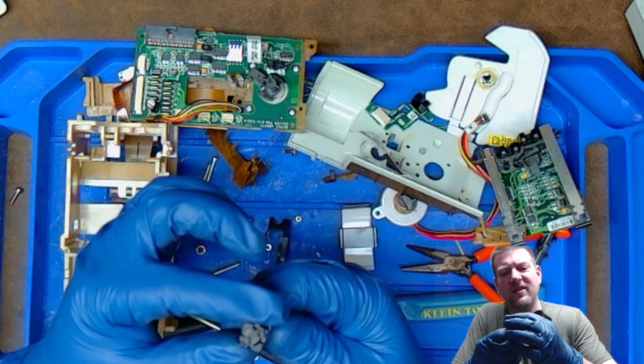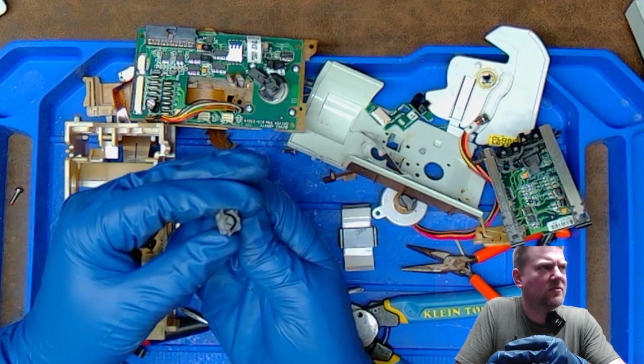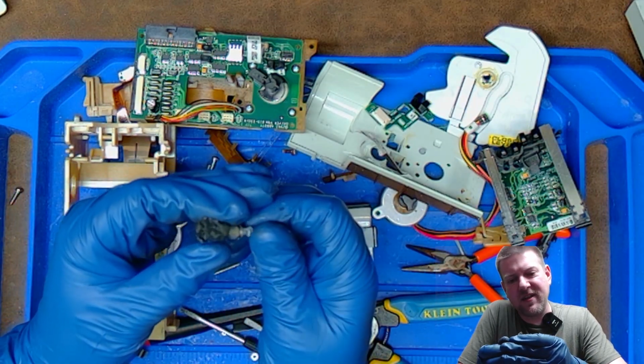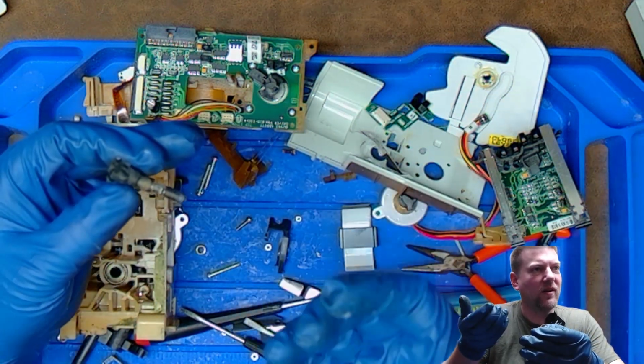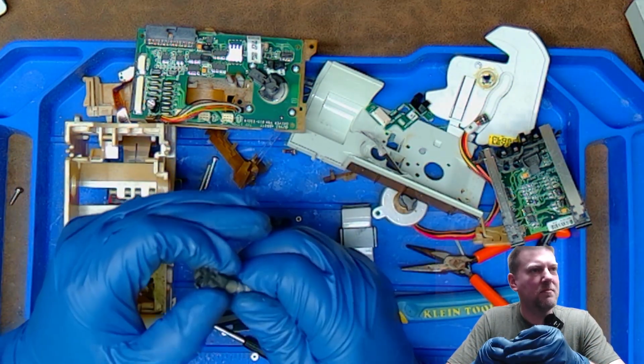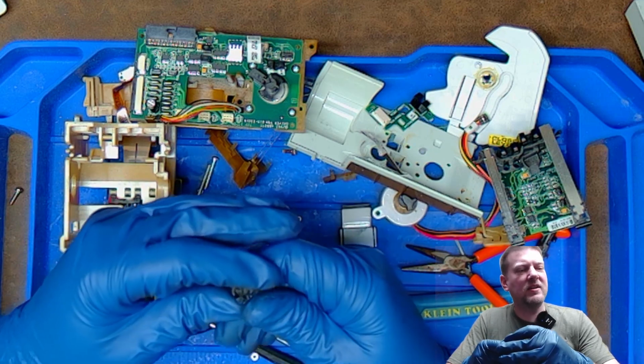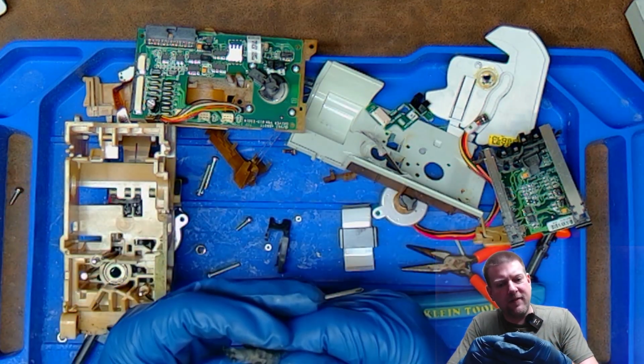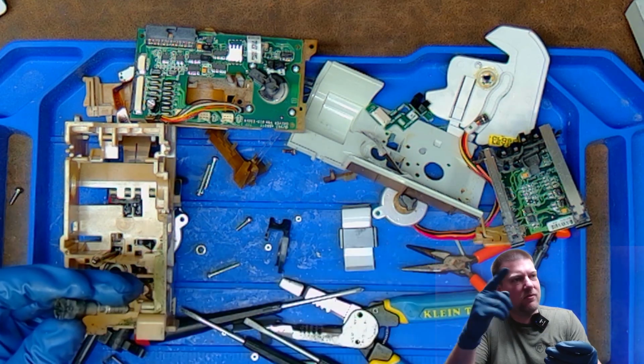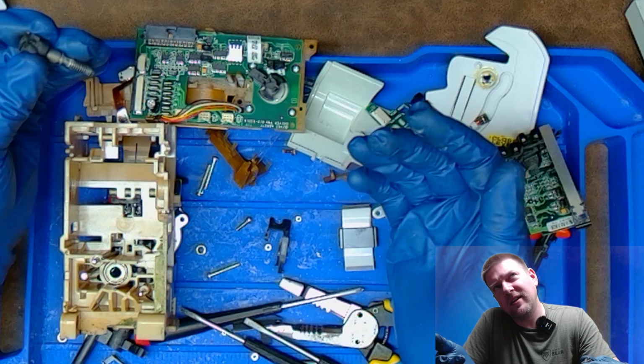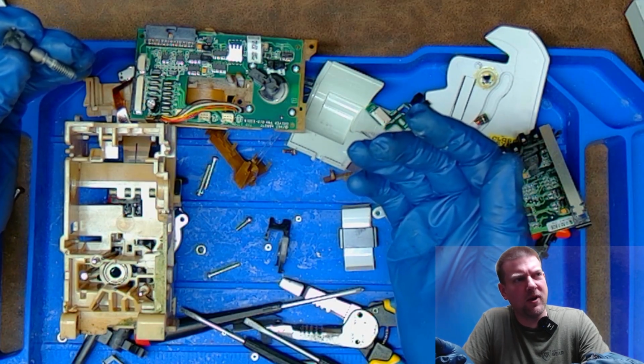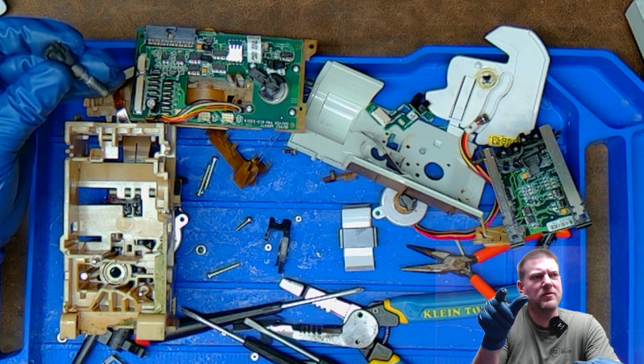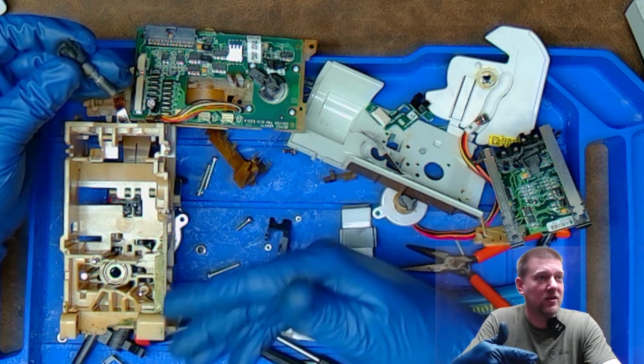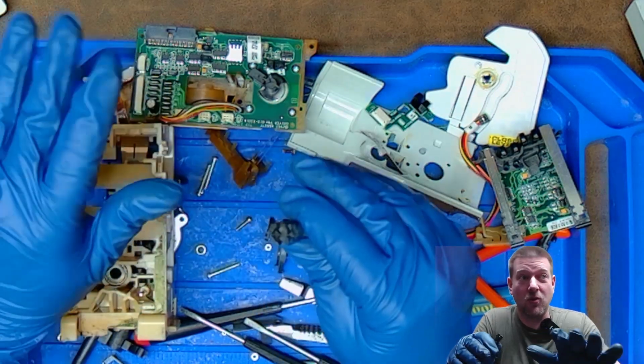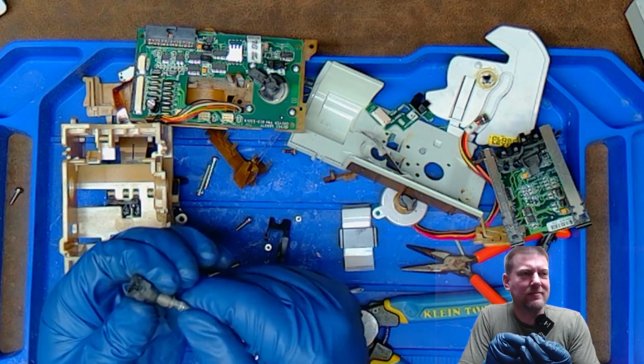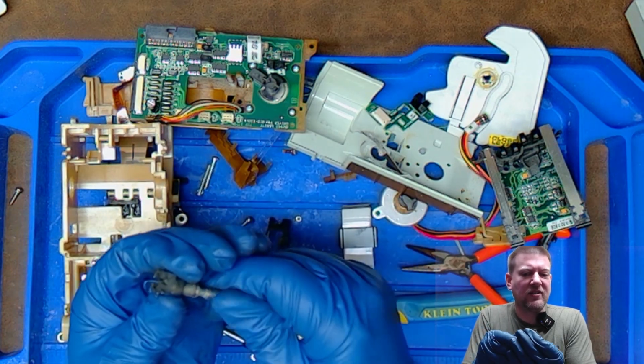And another interesting thing is, see how this comes up and locks? Now I'm curious if that comes up and locks like that when you open the door, because that way the plunger can't move, right? Or if that's the braking mechanism, because you know when it ends the infusion, if it pulls that lock out, so that it can't rotate and it can't distribute. I don't know what they call it, like a free run guard. You know how some infusion pumps, they clamp the hose so that it won't free run. In other words, keep distributing fluids to the patient when you don't want it to. I wonder if that's what that is. Kind of curious. But it's clearly some sort of lock.